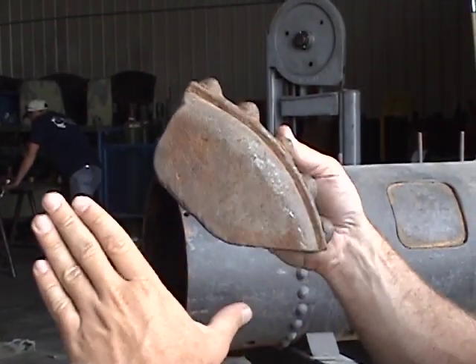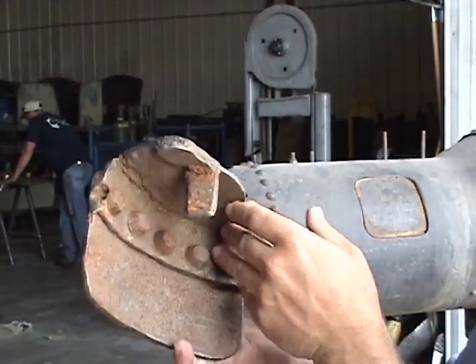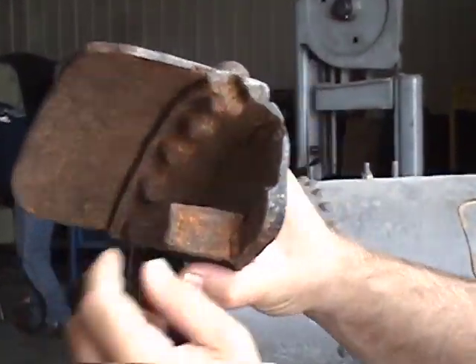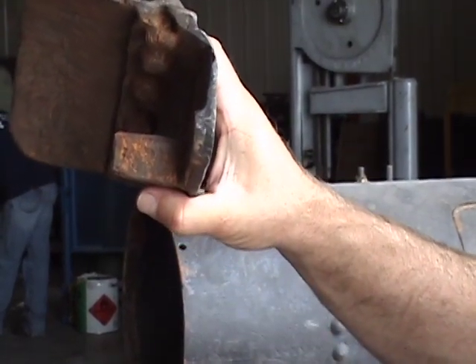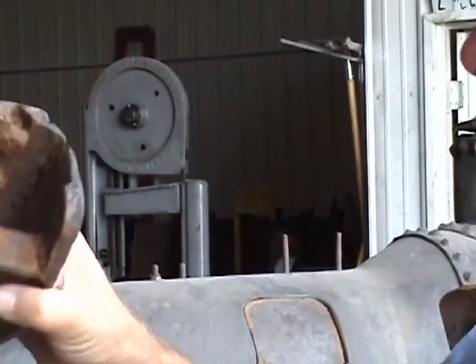Though the motion of my hand is quite exaggerated, this sheet is doing exactly that. In essence, what happens is the inside of the boiler that we can't see begins to tear and rip. And over the course of time, this ripping and tearing will actually thin the piece out so much that there's nothing left. So what looks good on the outside isn't necessarily always good on the inside. There are a lot of aspects of these old boilers, like this knuckle, that we simply cannot repair.